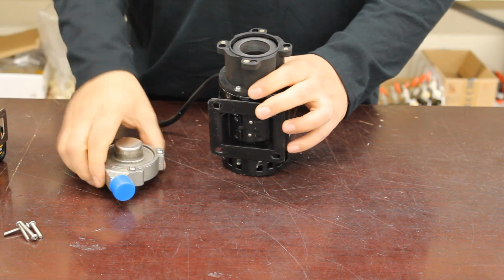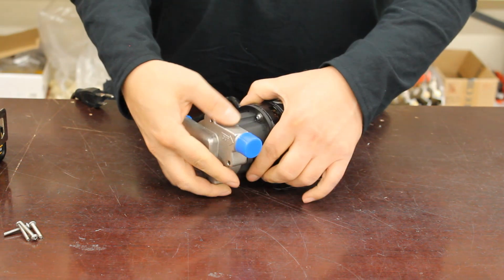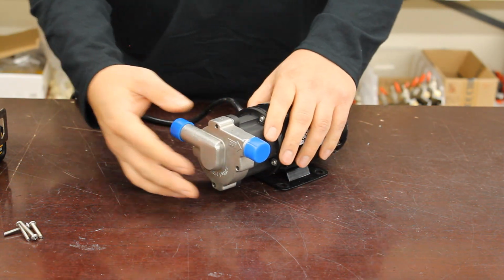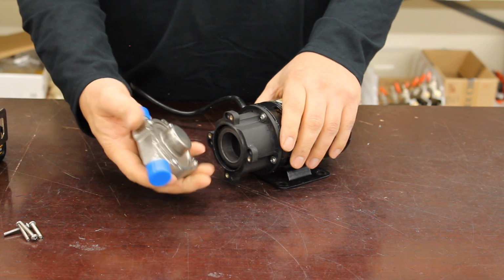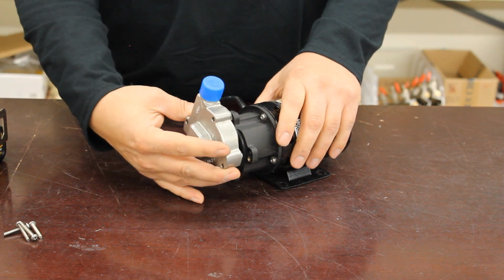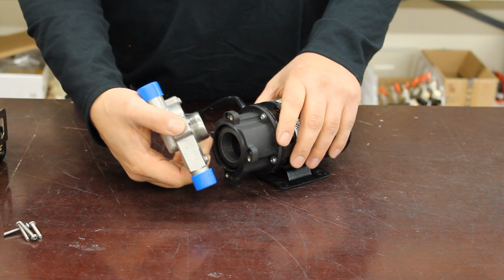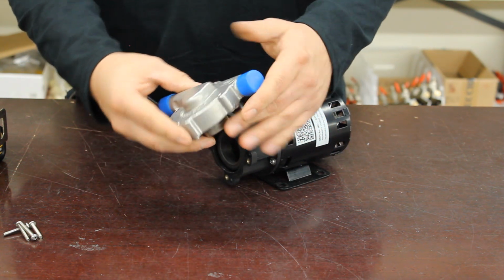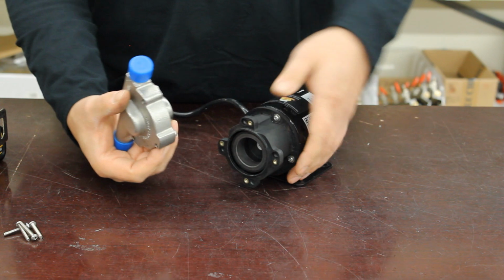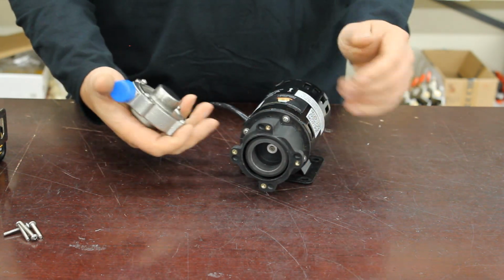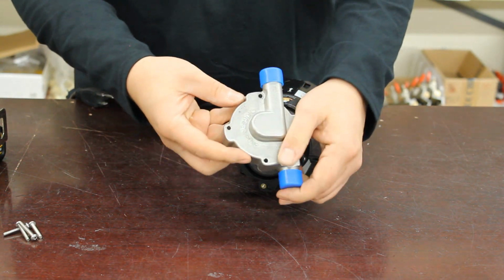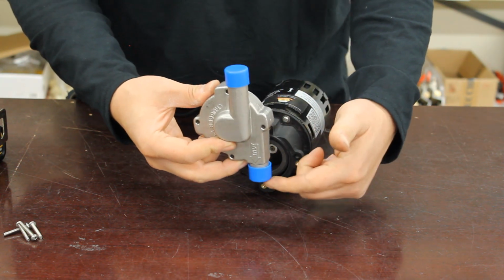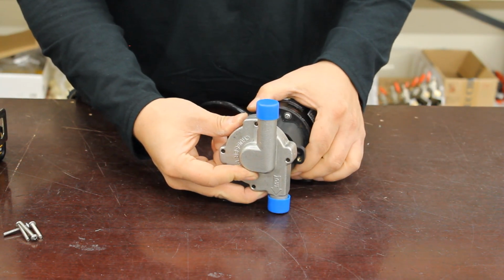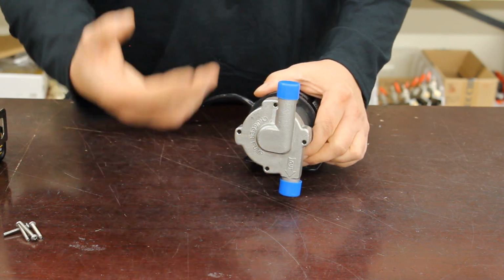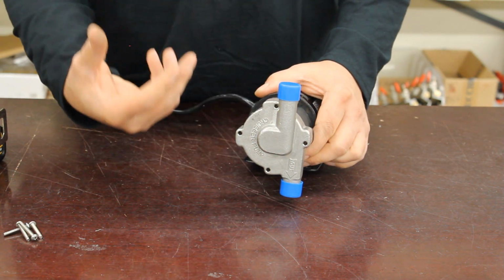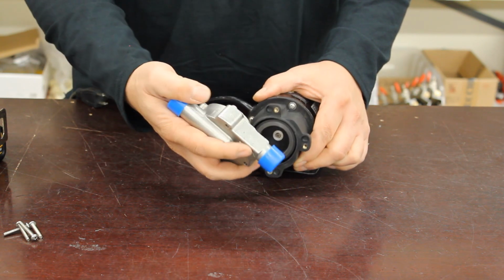So again, you can reinstall the head now that you've recentered the cup magnet. And I should mention also that at this point, you can also reorient the head in any position that happens to be convenient for your setup. One thing I do want to warn against, though, is that if the pump is being mounted with the bracket side down, what you don't want to do is position it so that the outside of the head is facing down. This is the most troublesome position as far as getting the head to flood with liquid and start pumping.